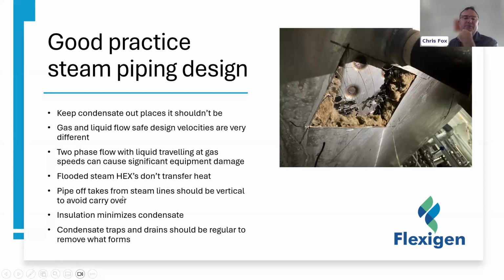All takeoff pipes from steam lines, it's actually the same with refrigeration systems, like with ammonia. Basically, you need to separate the gas from the liquid. All steam takeoff lines should be vertical, pointing upwards to avoid carryover into the user. Insulation minimizes condensate, so the more insulation you have, the less condensate you have to deal with. And also, condensate traps and drains should be regular to make sure it gets out before it ends up in your process.